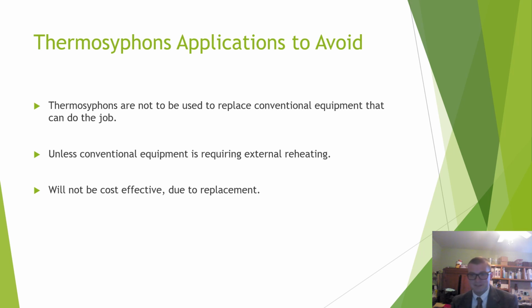Thermosiphons are not perfect. They are not to be used to replace conventional equipment that is capable of doing the job correctly. Unless the conventional equipment requires external heating because the inlet is being supercooled, it will not be cost effective, because you would have to pay to get the old equipment out on top of installing the new thermosiphon equipment, which isn't cheap on its own.